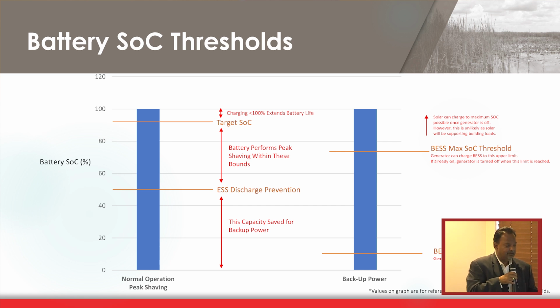Battery SOC stands for battery state of charge. So with a battery, you don't want to charge it to 100% because it loses its efficiency. You don't want to deplete a battery to 0% because, again, that shortens the lifespan of the battery. So we have this operating between 90% as maximum and 10% as minimum. In normal operation, between 50% and 90% state of charge, the ESS, which is the battery energy storage system, will be able to discharge to reduce the load whenever there are peaks or high points in the amount of draw from the grid.